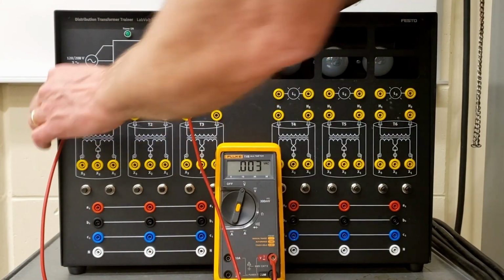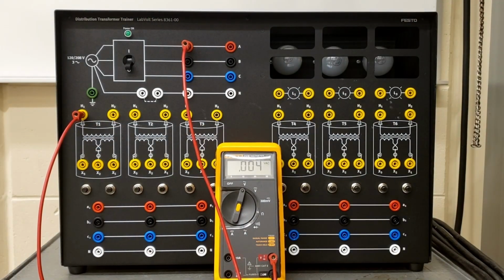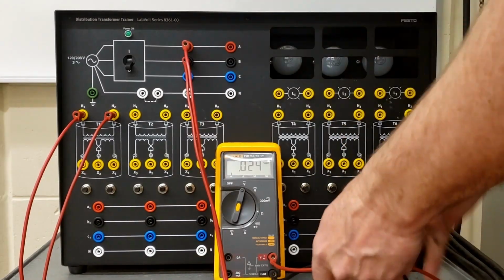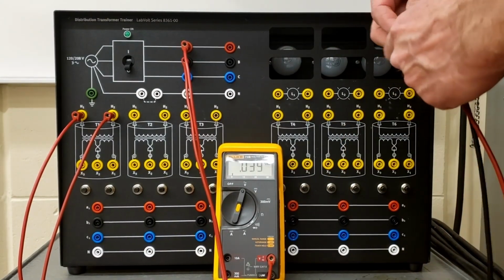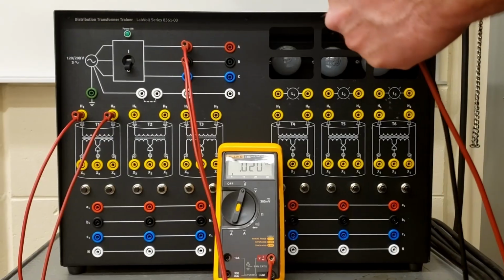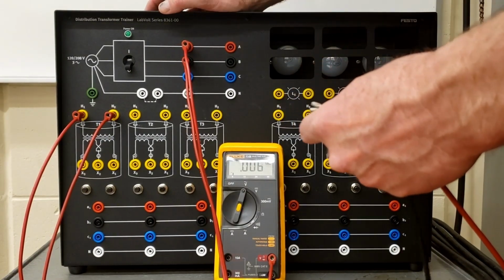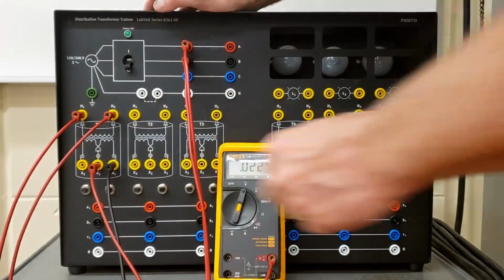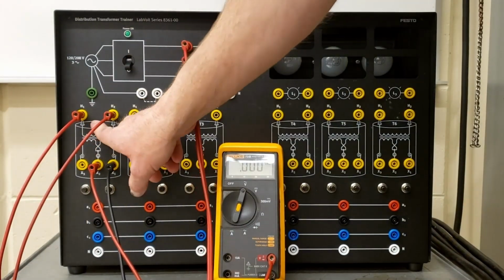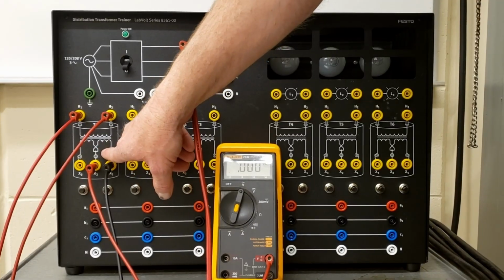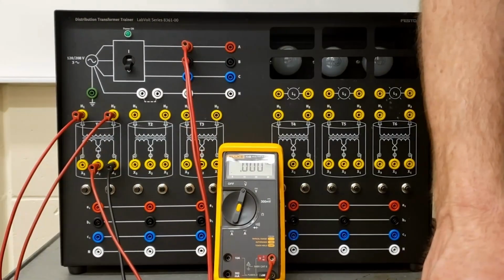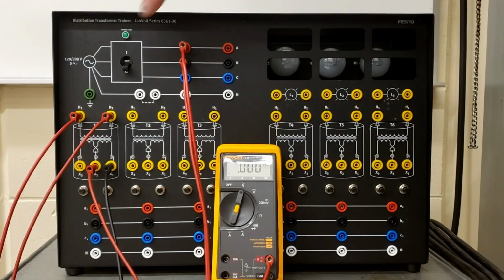So we're going to draw line 1 to X1 to H1, and then line 2 to H2. Then we're going to take a voltage reading from X1 to X2, X2 to X3, and then X1 to X3. First voltage there is X1 to X2. We have 208 here, and the ratio is that when we have 208 here, we have 120 and 120, because it's a root 3 relationship between those two. So we should have 120 volts on that secondary side.